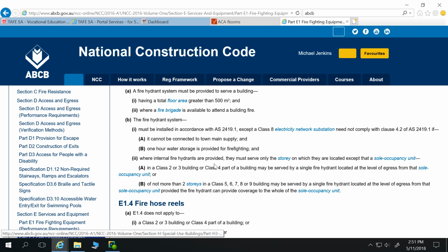The fire hydrant system must be installed in accordance with AS 2419.1, except Class 8, electricity network substation. They've got their own Australian standards. Except it cannot be connected to town main water supply, or we can connect to town main water supply, and 1 hour water storage is provided for firefighting. So our fire hydrant has to be installed in accordance with 2419. What I'm not expecting is for you to go into AS 2419, pull that apart and design fire hydrants.